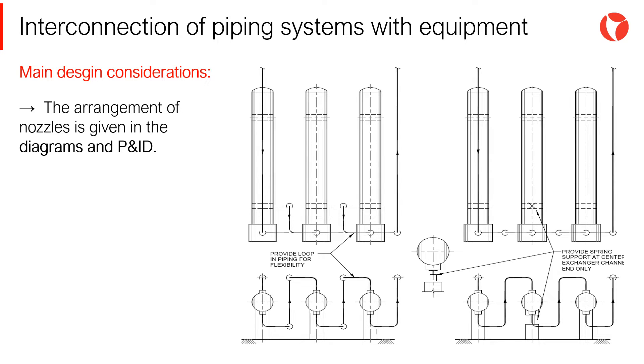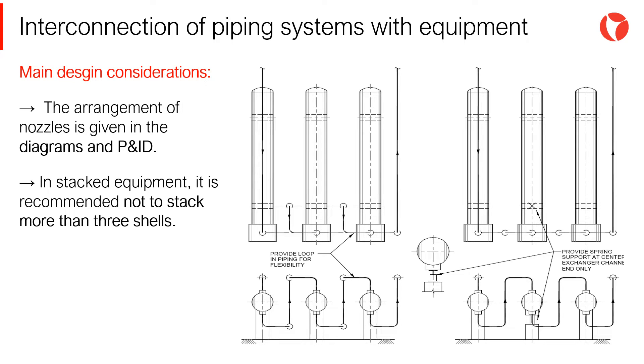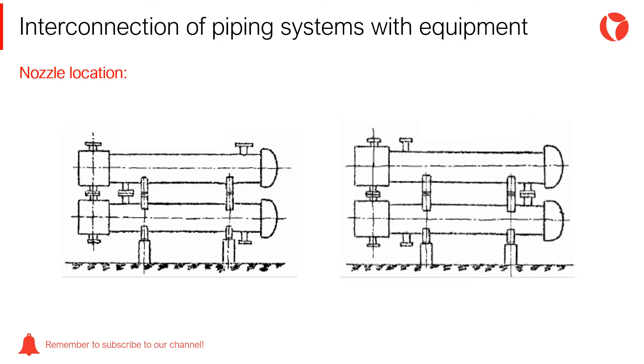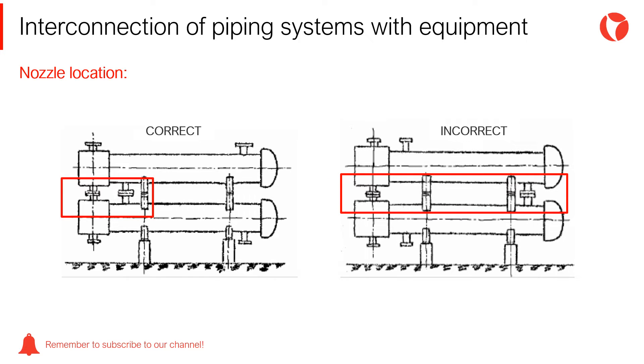The arrangement of the nozzles is given in the diagrams and P&ID. In stacked equipment, it is recommended not to stack more than three shells. The space in front of the exchanger should be free to allow for tube bundle extraction. In the case of stacked and interconnected exchangers operating in series or parallel, nozzles to be connected will be located as close as possible to avoid excessive stress or expansion differences between shells.